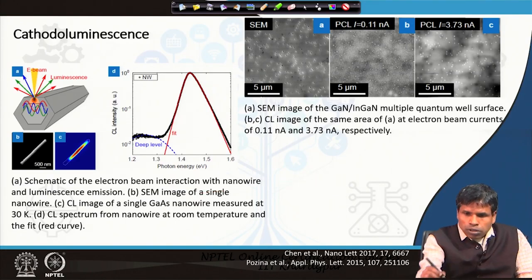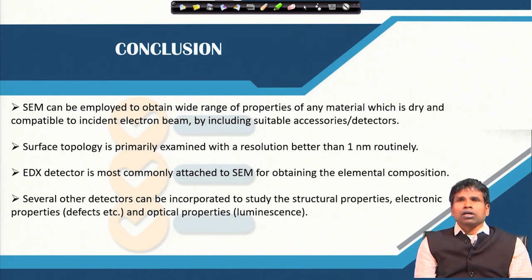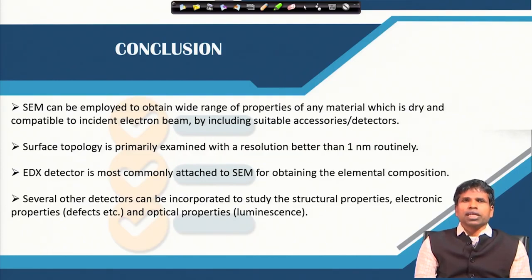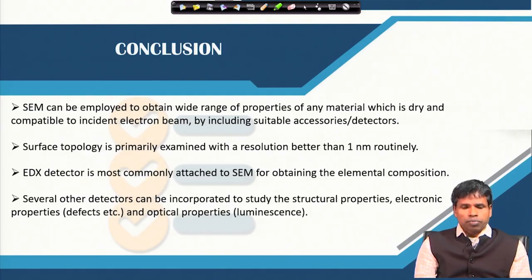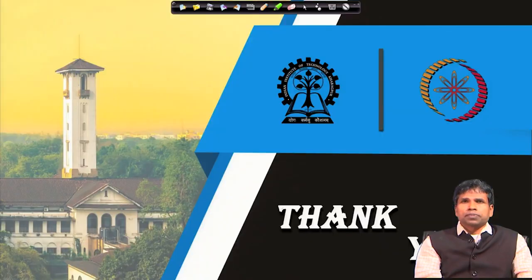In conclusion, the scanning electron microscope can be used for many purposes provided suitable detectors are attached. Primarily it examines surface topology with resolution better than one nanometer using field emission SEM. With suitable detectors, structural properties such as crystallinity, crystal structure, and grain orientation can be studied via EBSD. Electronic properties such as defects can be studied via EBIC, and optical properties such as band gap and luminescence can be studied via cathodoluminescence. These are the diverse types of studies that can be performed with a scanning electron microscope.